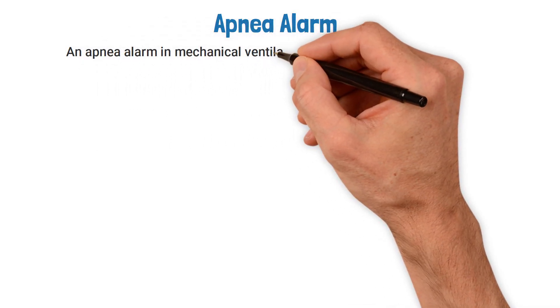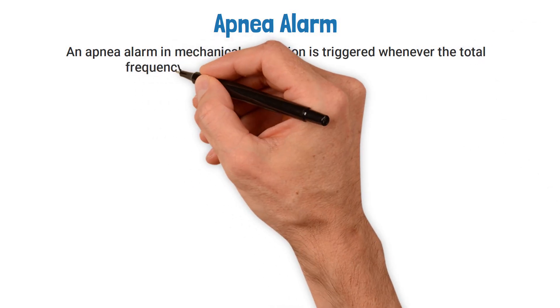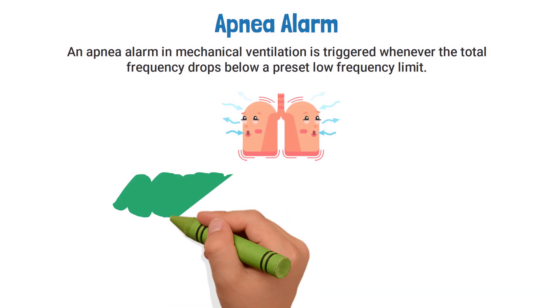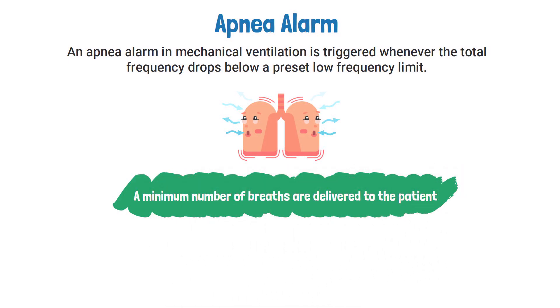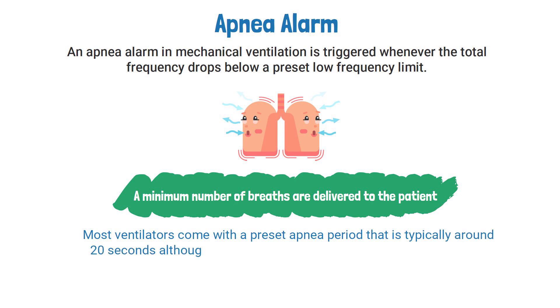An apnea alarm in mechanical ventilation is triggered whenever the total frequency drops below a preset low frequency limit. This is useful in ensuring that a minimum number of breaths are delivered to the patient. Most ventilators come with a preset apnea period that is typically around 20 seconds, although some allow the operator to adjust this time limit.